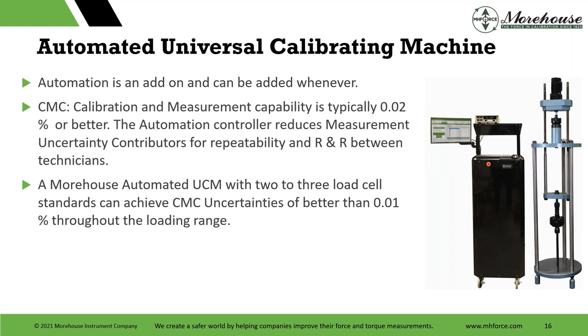And then a Morehouse automated UCM with 2 to 3 load cell standards can achieve CMC uncertainties of better than 0.01% throughout the loading range. That is another business case people need to make. Do I want to be switching? Do I want to take higher uncertainties and switch fewer standards, or do I want to make several switches of standards?